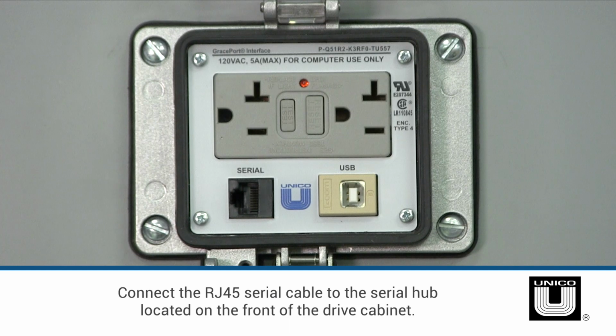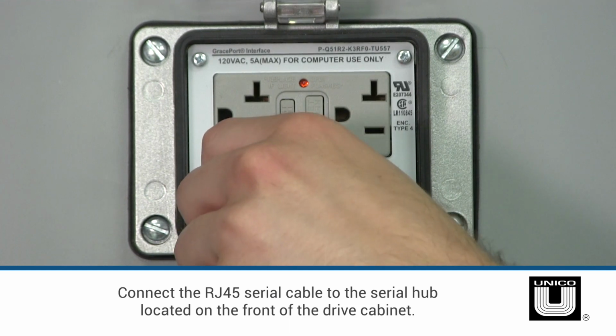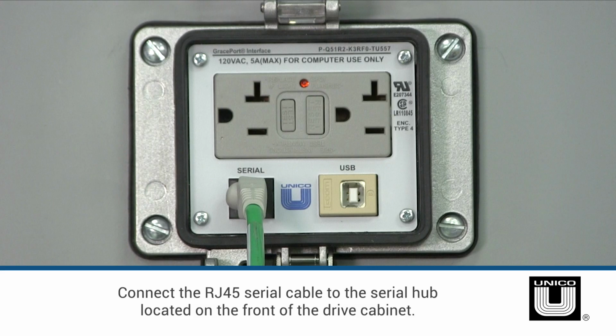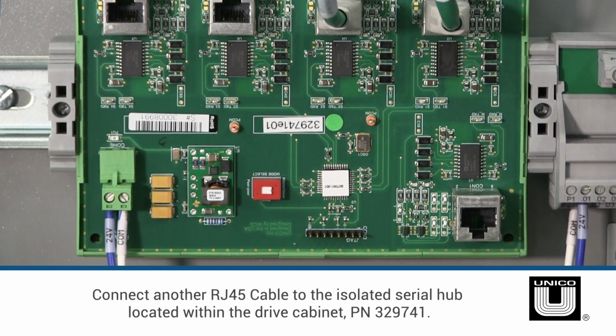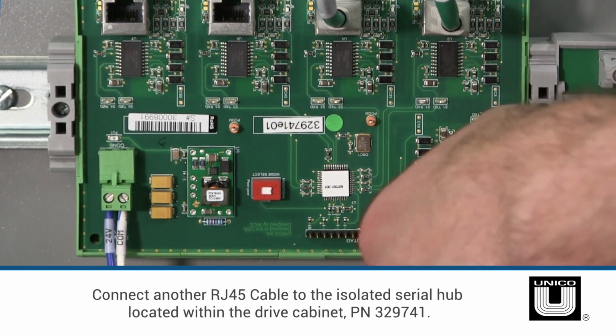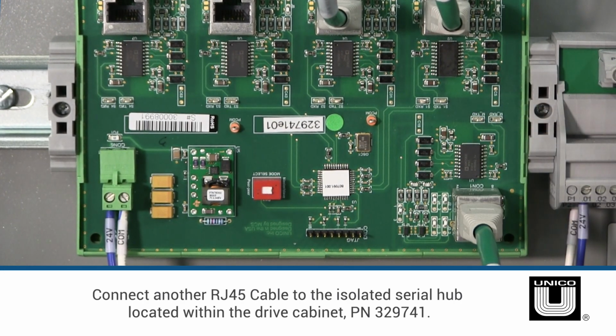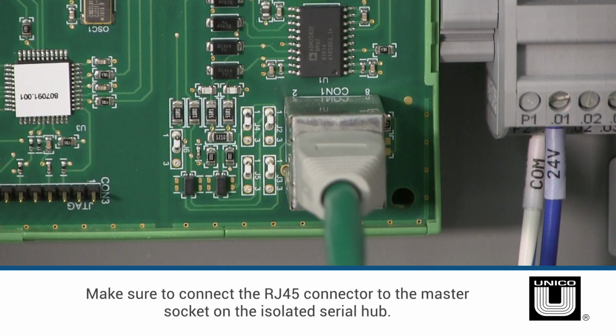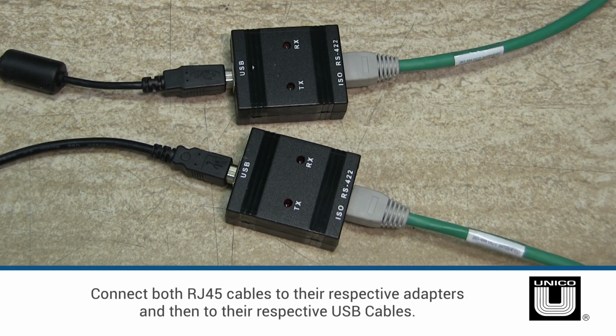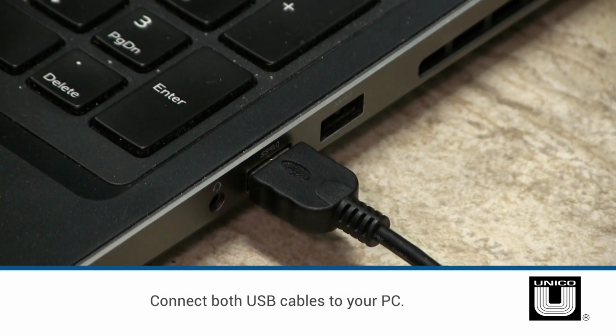For communication to the DSP module, connect the RJ45 serial cable to the serial hub located on the front of the drive cabinet. Similarly, for the DCR5 module, connect another RJ45 cable to the isolated serial hub located within the drive cabinet, part number 329741. Make sure to connect the RJ45 connector to the master socket on the isolated serial hub. Then connect both USBs to your PC.